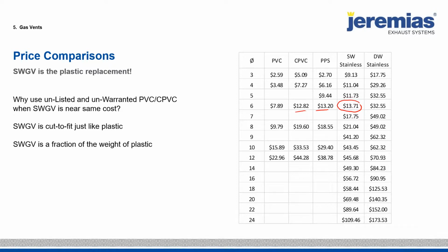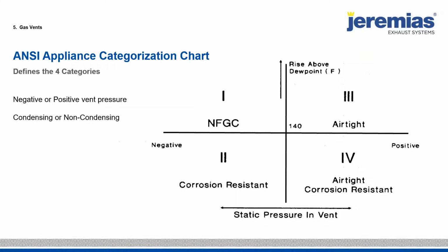Of course, the United States is the only country in the world that allows non-listed PVC to be used. Up in Canada, only listed systems. All throughout Europe, they have nothing like PVC or CPVC there. Everything is polypropylene because it's 100% recyclable, or stainless steel. Stainless steel is actually coming back on the condensing side, becoming more popular than polypropylene throughout Europe.